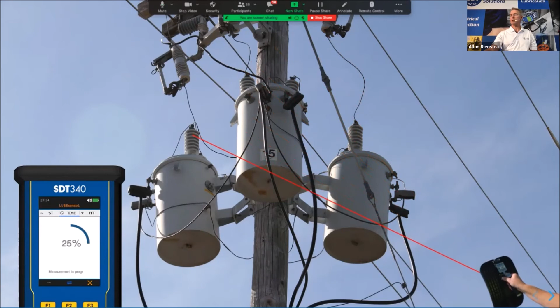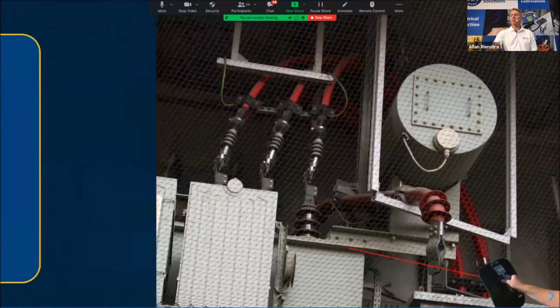Each of these time waveforms can also be looked at in the spectral view. In North America we'll see peaks every 60 hertz, which is the line frequency. In Europe or other countries, we'll see those same peaks but at 50 hertz. This helps us determine whether the problem is related to corona, arcing, or tracking. Doing deeper analysis and assessment allows our planners to decide on scheduled maintenance and what kind of maintenance they'll need. A lot of times with corona discharge, it's just a matter of getting the dry ice out, cleaning it, and restoring it.